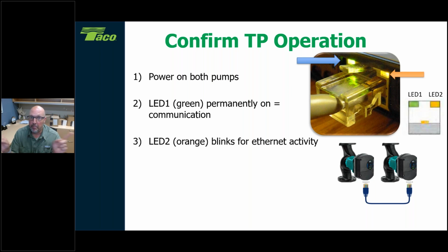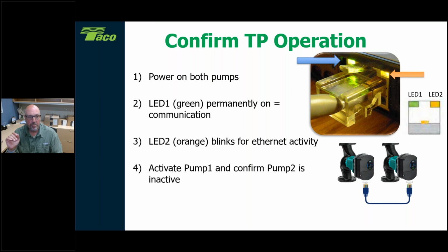That means we're communicating between 2 devices. If you don't see orange, but you got green, well, we got some communication that's happening, but they're not sending backwards. So they're not talking to each other. So confirm the LED lights that are on the circulator itself. Very, very important. Now you want to make sure it's doing what it's doing before you leave. Turn on pump 1, and then make sure that pump 2 is inactive. The faceplate should be lit up. It should have power on the faceplate, but it should be all zeros as it scrolls through, and you'll see that pump number 1 is running, and you should have some numbers on there.